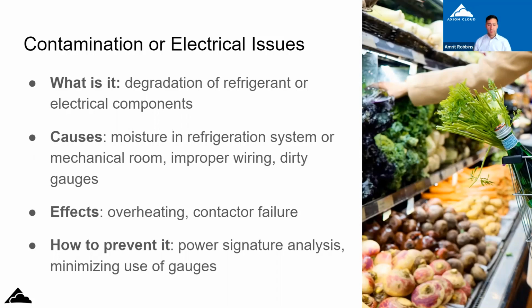So Joe, how prevalent are corrosion issues when you're going to these mechanical rooms? Like contamination. A lot of them. I'd say contamination more, not corrosion as much. You'll see a lot of dirty oil, which can come from any of these things we just talked about. Heat also breaks down the oil and makes it eventually become pretty acidic, just from cooking it essentially. I think one of the things that goes overlooked a little bit is the quality of the oil in a system. It's the main thing. It lubricates the compressors. And if it's compromised in any way, your compressor's not going to get proper lubrication. Like Trevor said, the safeties are in there for a reason. It's like an oil failure is at the minimum of what the oil pressure is supposed to be.